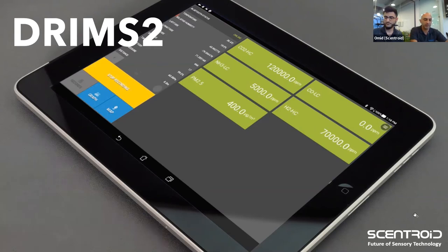They're looking at the current going through it and the voltage it gives back. So if you don't plug in an electrochemical sensor, the system will recognize the current and power consumption issue, so it will not provide you with PPB readings - you will see that it's a fault, you'll get no data reading from that sensor. So it has this kind of fault detection built in. If the sensor is not even responding properly, you will get this fault detection.